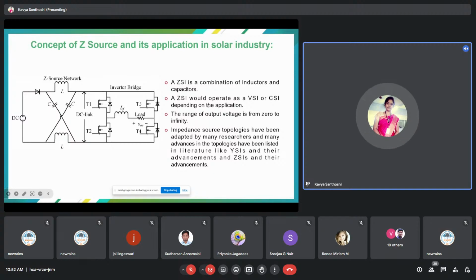Generally, when we operate our inverter, we have T1, T2, T3, T4 switches and the load. Usually we operate T1 and T4 together, meaning no two switches from the same arm or leg operate together. T1 and T2 are on the same arm, and T3 and T4 are on the same arm. So no two switches from the same arm should operate at the same time.